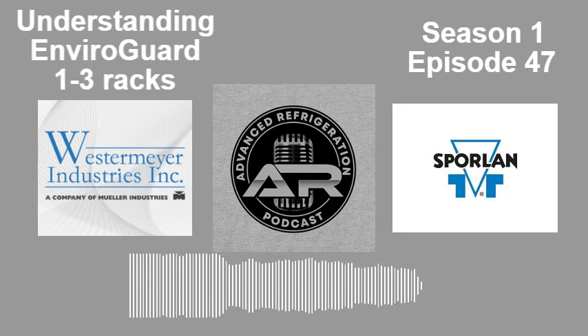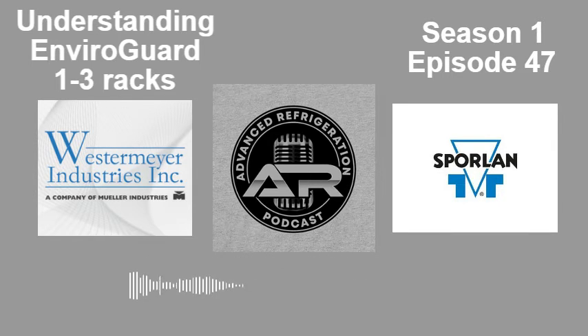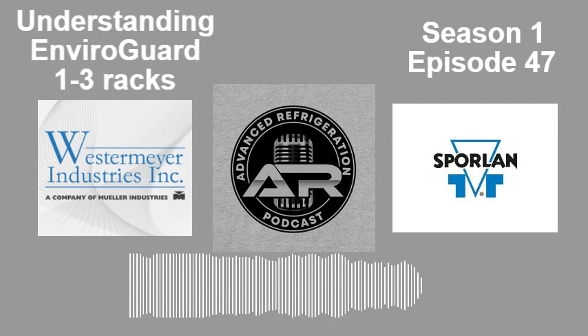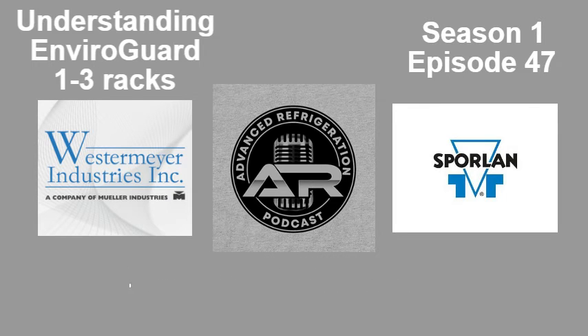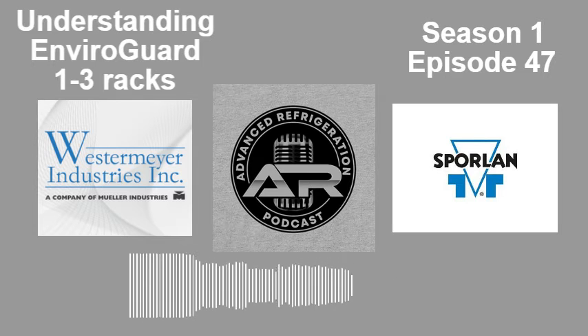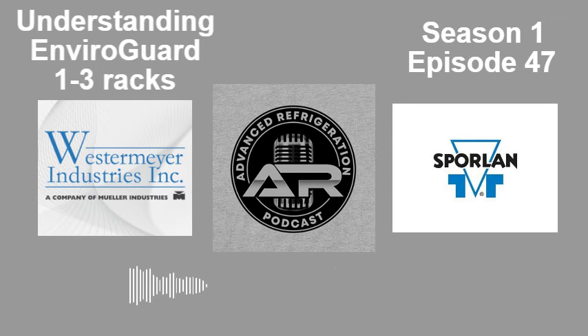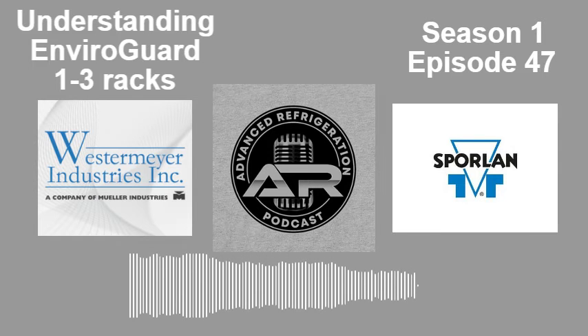So if you were floating the head, you were floating the subcooling set point as well, correct? Yes. Okay, so you were doing floating head, using the approach on the condenser, and then on top of that, you'd also be floating the subcooling. Maybe it's another subject, but I'm just kind of confused how the two weren't trying to fight each other. Meaning the floating head or the floating TD? Because if it tries to achieve the pressure, you have to basically run it down. But I guess if you're floating it off the ambient, the TD is correct. Never mind.